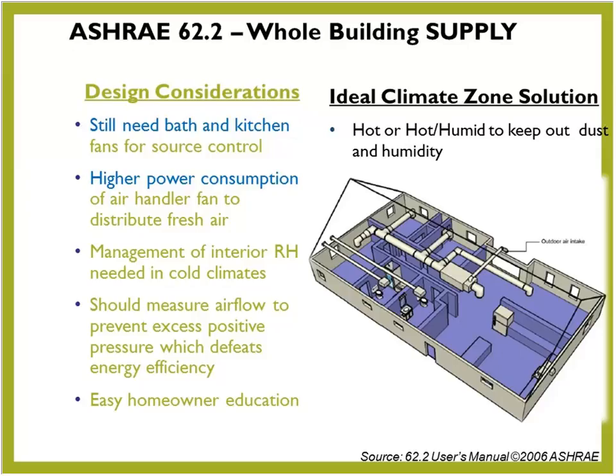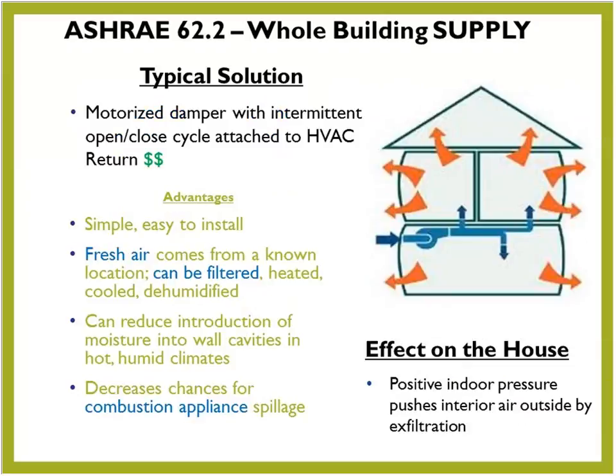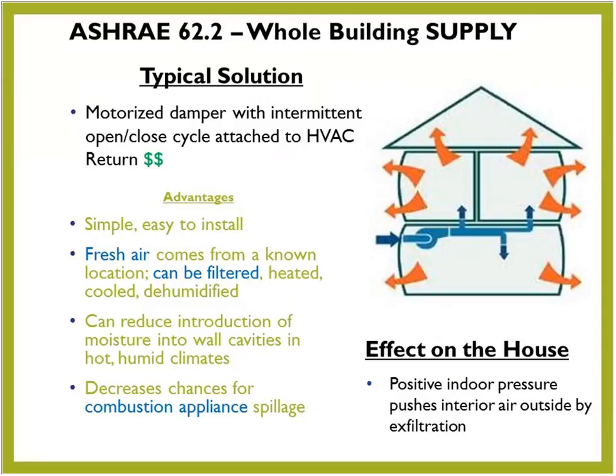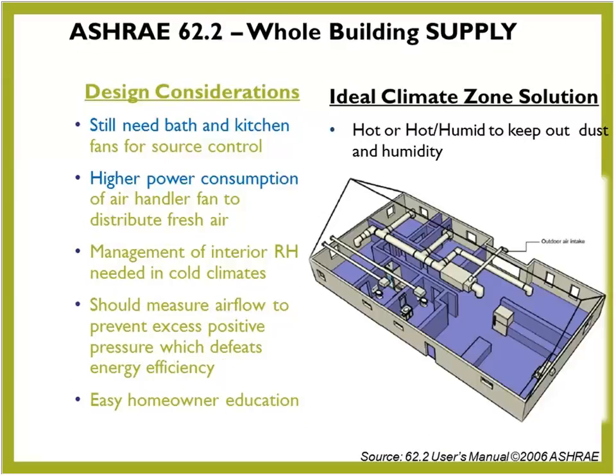Again, because we're going to be putting a little bit of pressure on the home with the supply-only approach, we're going to be requiring that air leak out of the building somewhere, and generally it's going to be through the building shell or under a doorway or whatever. So again, one of the cautions for this approach is that we don't want to create too much positive pressure and force that indoor air. It's stale, it needs to be exhausted, but it's also carrying some moisture with it.